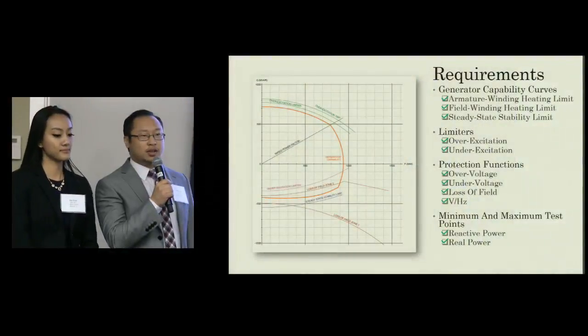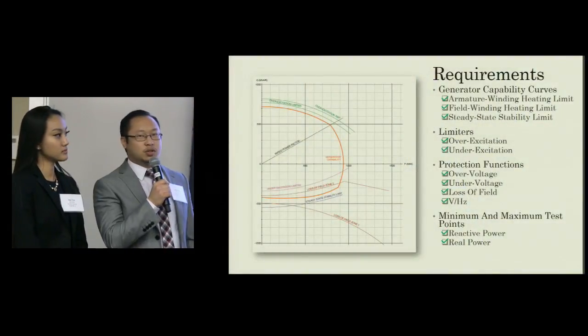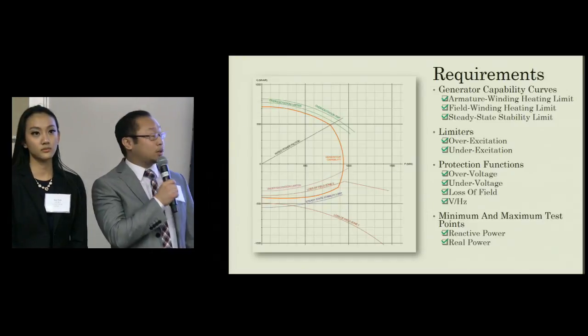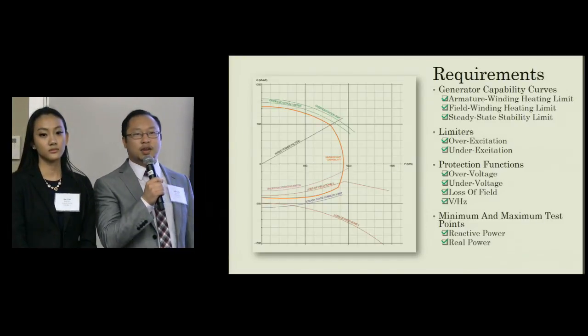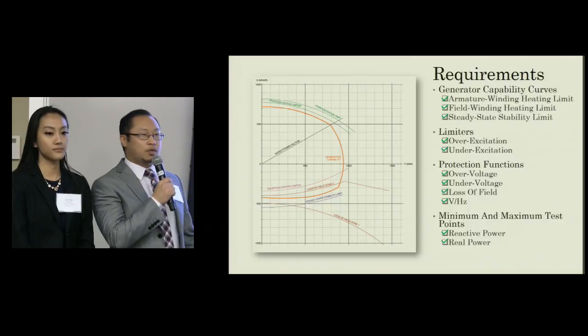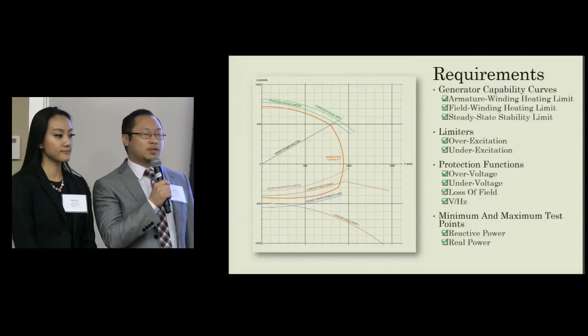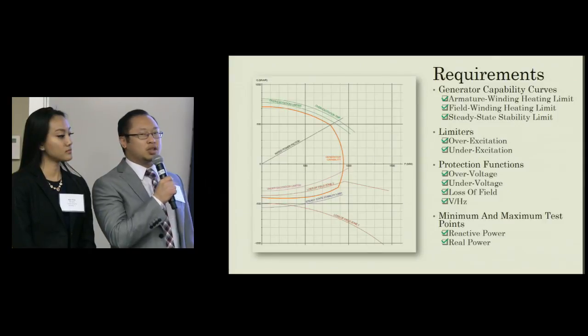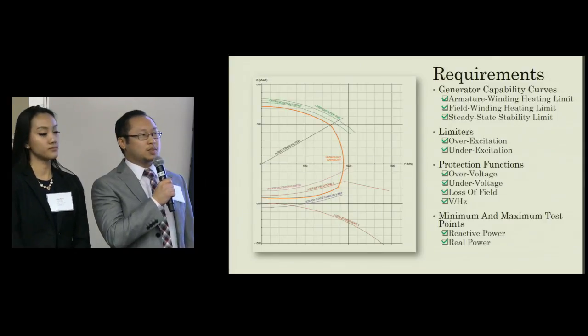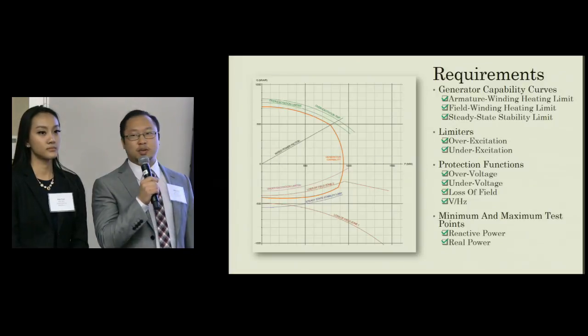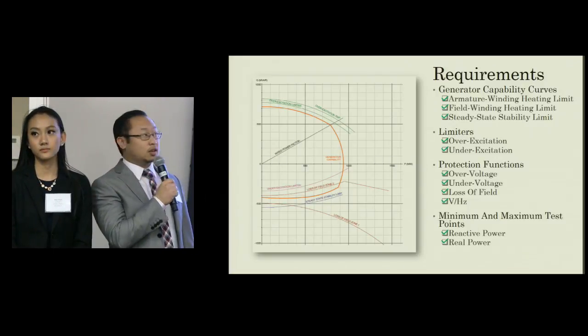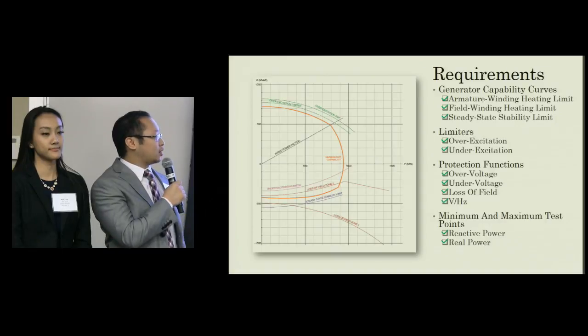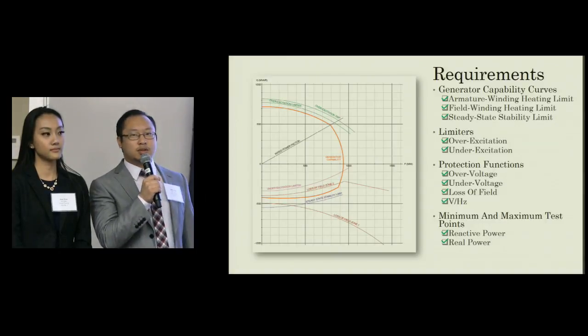Aside from the 3 generator capability curves, our tool needed to be able to plot these other things. The over-excitation and under-excitation limiters prevent the generator from operating too close to the field winding heating limit and the steady state stability limit. Protection functions can activate if excitation systems fail. Over and under voltage protection can activate when a sudden load interchange occurs and the voltage spikes up or dips too low. Loss of field protection activates if the under excitation system fails and the stator and rotor lose synchronism with each other.